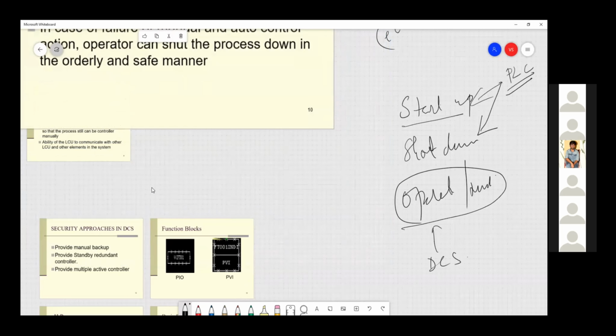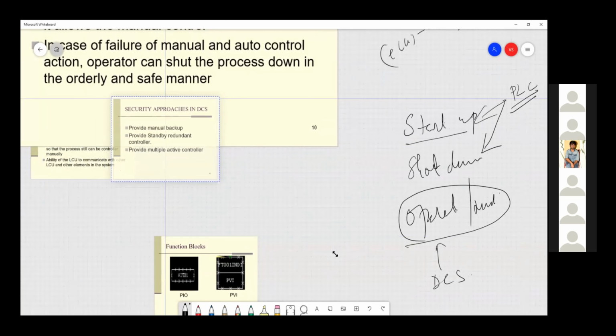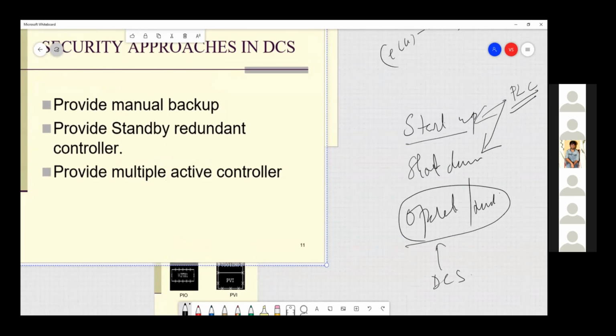So normally this is the hierarchy: you can have a manual backup, a standby backup or redundant control, and sometimes multiple active controllers also—manual backup, standby redundant, or multiple active—whenever the cost is acceptable, or for critical information. Sometimes from a safety point of view, sometimes for operational comfort, some loops become critical and some non-critical. In that scenario, you can have multiple active controllers instead of just two. That's a major concept.